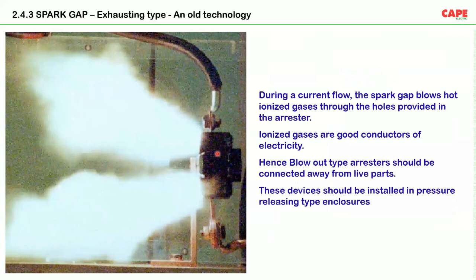The spark which is created inside the gap will blow out as a flash, for example. During a current flow, the spark gap blows hot ionized gases through the holes provided in the arrestor. Actually, these arrestors were discontinued several decades back. But why I am showing this is these devices are still sold in India because the OEMs in India don't look at the safety parameter of the component. They always look at the price of the device. As a result, these devices are still sold in India.